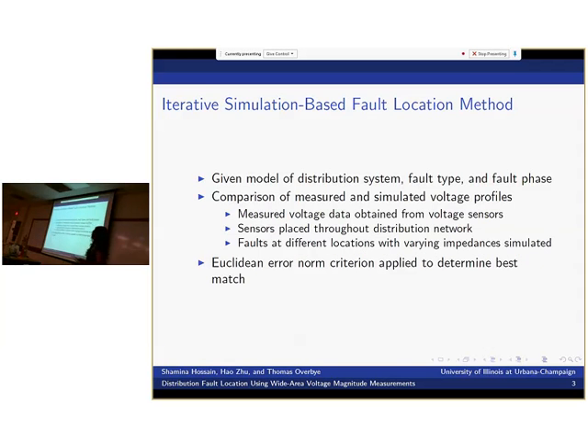And so today I'm going to be presenting an iterative simulation-based fault location algorithm for distribution systems. Given a model of a distribution system and the fault type and fault phase, from the voltage sensors placed across the network along the lines, I would get a measured voltage profile given that a fault has occurred, which at the control center you could be notified of by sudden changes in voltage. Once I get that measured voltage profile, in each iteration I will simulate a fault at a certain location with certain impedances of the same fault type and phase, and compare these two profiles using the Euclidean error norm criterion. Using that norm, I will find the best match between the two and thus find the location and impedance of the fault that has occurred in the system.